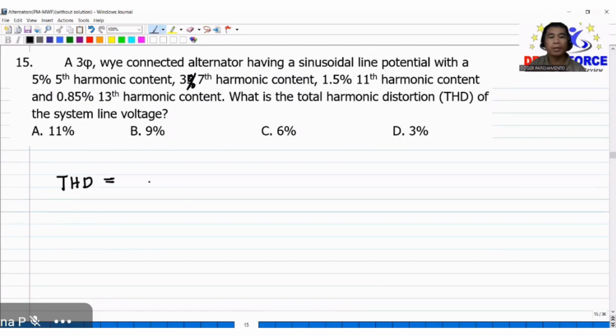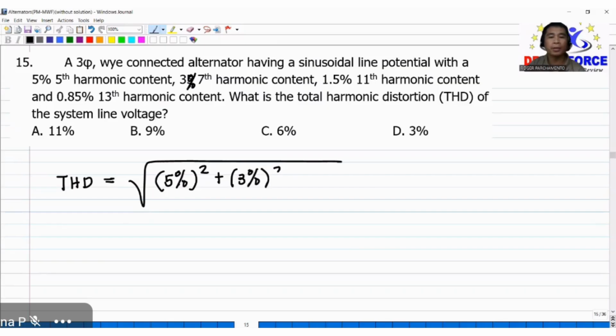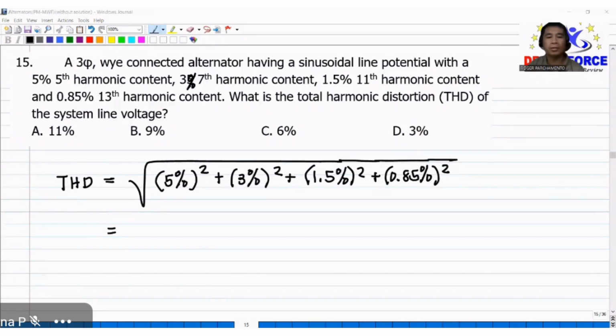THD is equivalent to the square root of the percentage harmonics squared. That will be 5% squared, then plus 3% squared, then plus 1.5% squared, then plus 0.85% squared. Okay? So that is percent squared, then square root.